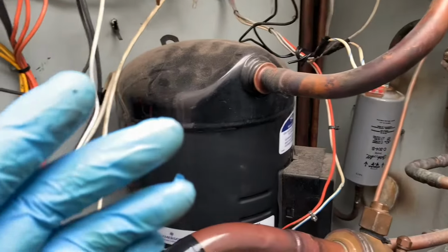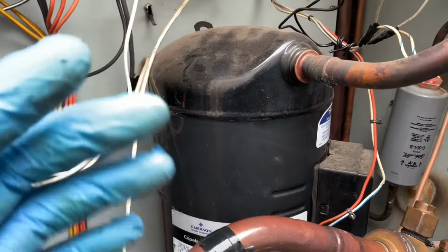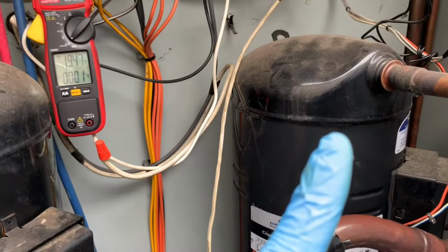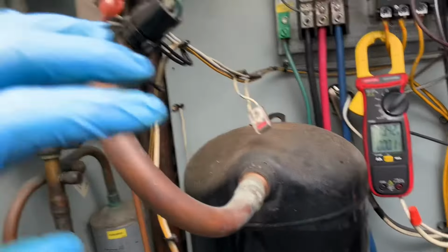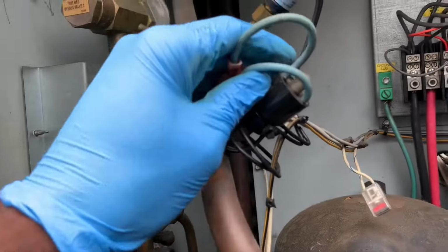Sometimes you've got multiple compressors, but they're in tandem, okay? If they are in tandem, then two compressors together in tandem is still one circuit, so even though you have two compressors, you'll only have one high pressure and one low pressure on those two compressors. But in this particular case, they're not piped in tandem, they're separate circuits. So we've got one high pressure, and if you can see here, there's a manual reset on this one right here.